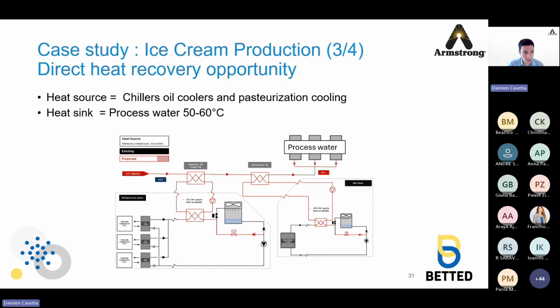So basically what we are doing here is that we are heating water, which comes at 10 degrees, first going through oil coolers, heat recovery, and then pasteurization. So we go from 10 to 50, 60 degrees by direct heat recovery only. So the only consumption is pumping. No heat pumps, no fossil fuels, only pumping and heat exchangers. That's the first step.